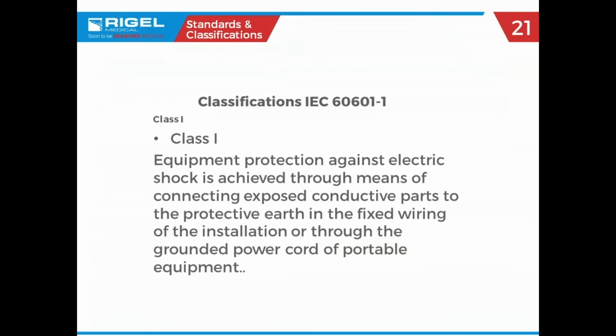So classifications. FDA has their own classifications, which are nowhere similar to these classifications. So from medical device testing, we talk about class 1 devices. The easiest, fastest way to determine if you have a class 1 device? Ground pin. We depend on that ground pin to take any stray currents away from the medical device and shunt them to ground. So anything with a ground pin is tested as class 1.